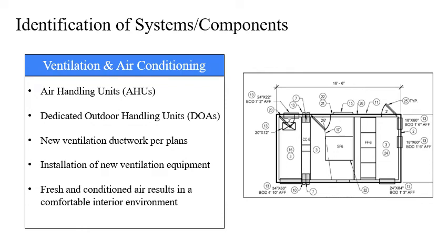The ventilation system in Everett consists mainly of air handling units, as shown here, and dedicated outdoor air handling units. These two components regulate air within the building through extensive ductwork with the aid of motorized fans, air filters, diffusers, and exhaust grills. The AHU takes air in from the outside using a supply fan and passes it through a filter to purify it. The air then passes through a heating or cooling coil depending on the system requirement at that time. All exhaust from the system is removed in the process, and the AHU then uses return fans to send the fresh, reconditioned air to the rest of the building through the ductwork.